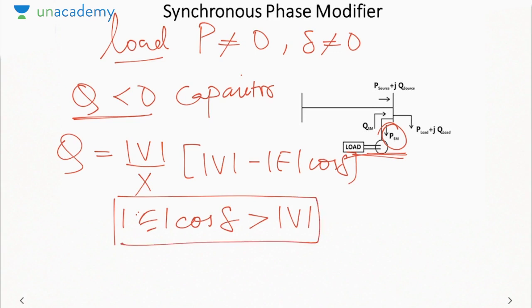Okay. So the thing is, suppose I have a synchronous motor which I am using for power factor correction. Then I have a small load to drive. Instead of buying an additional motor or bringing an additional motor into the system, why not drive such a small load, which is maybe used temporarily, with the help of the synchronous motor? That will make use of the mechanical power of the synchronous motor, or the mechanical part of the synchronous motor. That is why the synchronous motor is more advantageous. If you have a small mechanical load, you can drive it alongside and you can also have the power factor correction or the voltage control.